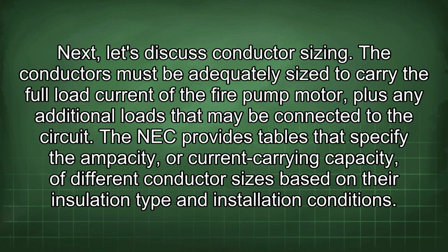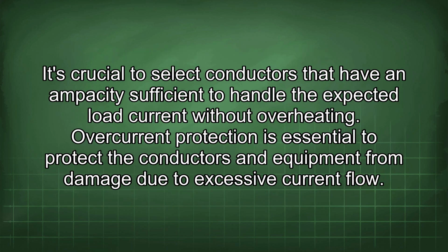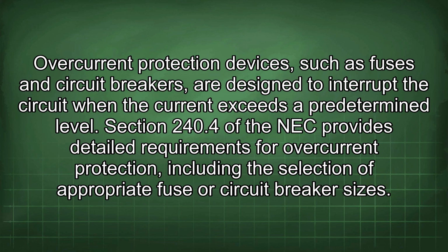The NEC provides tables that specify the ampacity, or current carrying capacity, of different conductor sizes based on their insulation type and installation conditions. It's crucial to select conductors that have an ampacity sufficient to handle the expected load current without overheating. Overcurrent protection is essential to protect the conductors and equipment from damage due to excessive current flow. Overcurrent protection devices such as fuses and circuit breakers are designed to interrupt the circuit when the current exceeds a predetermined level.